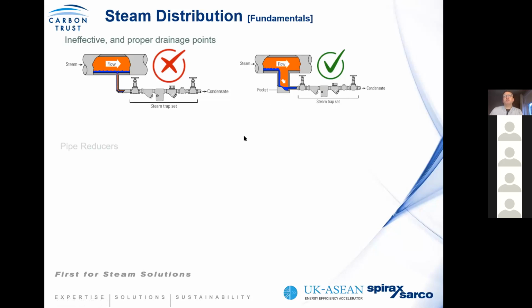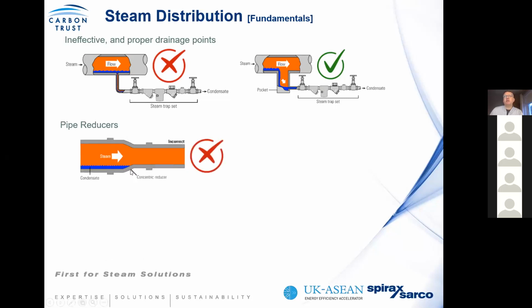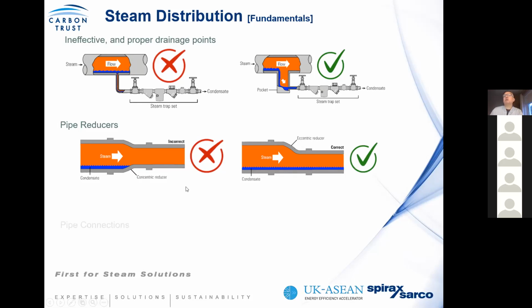When we start looking at pipe reducers, because again, we distribute a certain pipe size, and what we do is we reduce the pipe dimensions as we move out towards the index parts of the distribution system. Often we see these ineffective concentric reducers, and what you would see is that you create a sump of condensate sitting on the lower part of the larger pipe. What will happen is that under certain velocities, you will end up dragging this water or condensate like a wave into the distribution system, creating water hammer problems. And we will discuss water hammer in more detail in a minute. So when it comes to reducers, it's important that you have an eccentric reducer such that the condensate can move freely along the base of the steam distribution pipe. Where you have the effective dirt pocket, it can be removed more effectively. We also should look at the pipe connections.